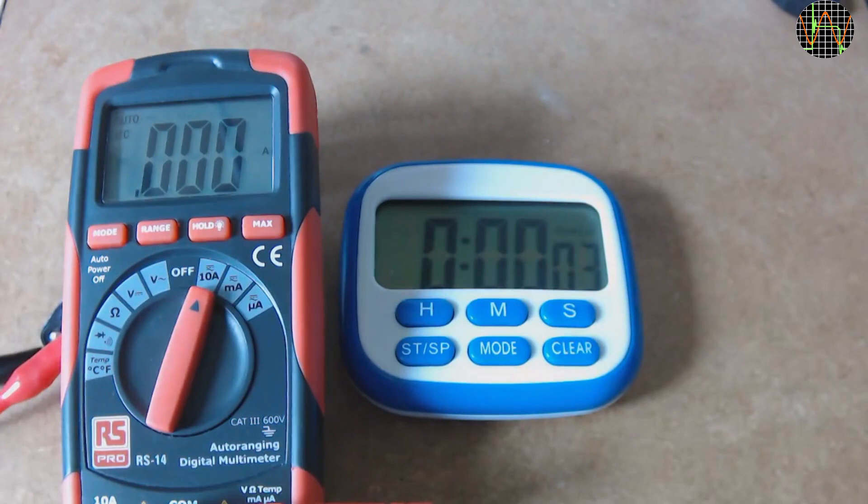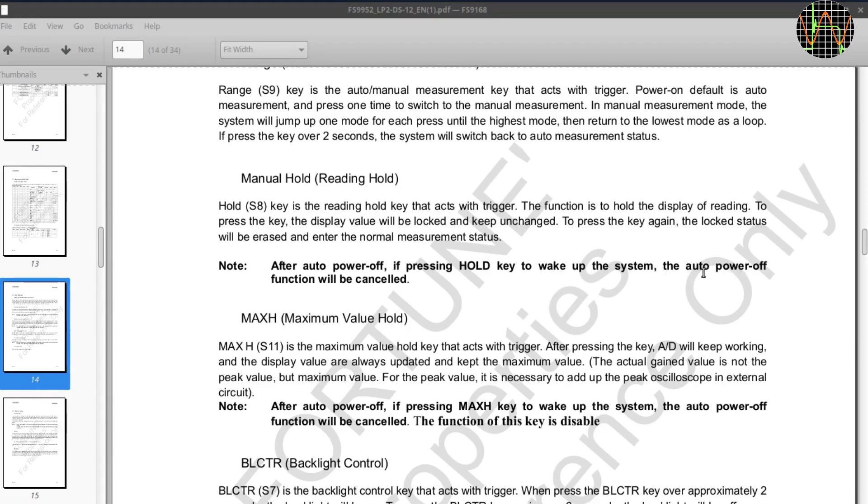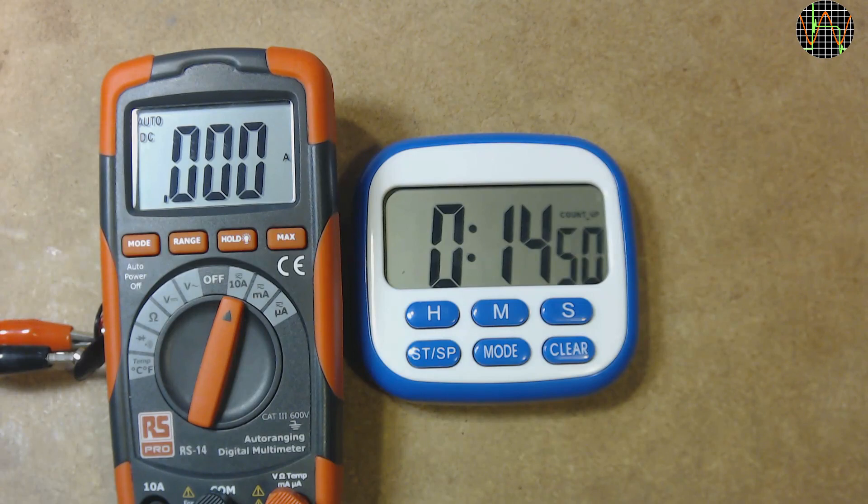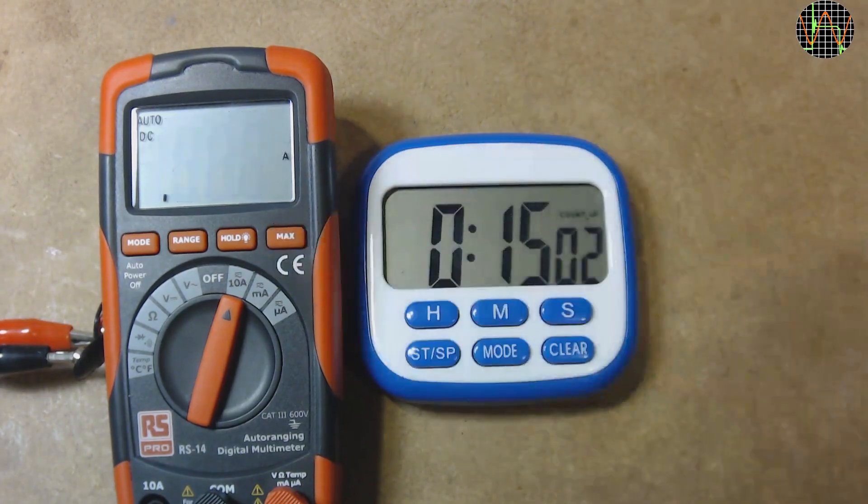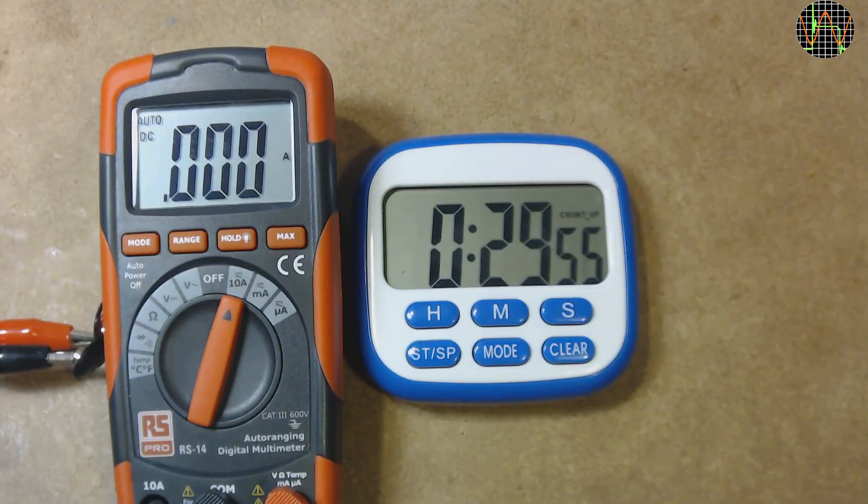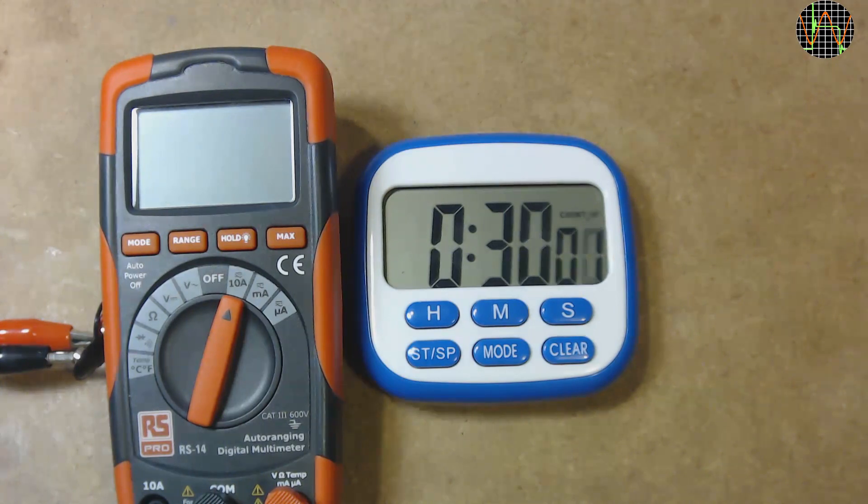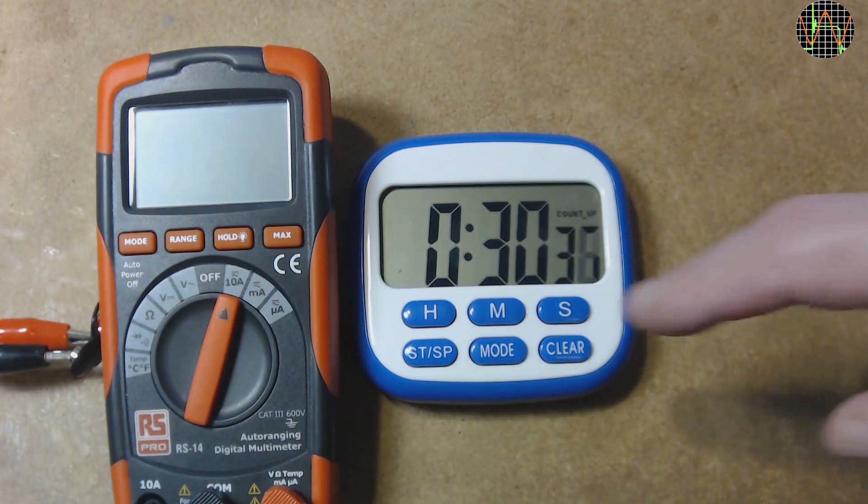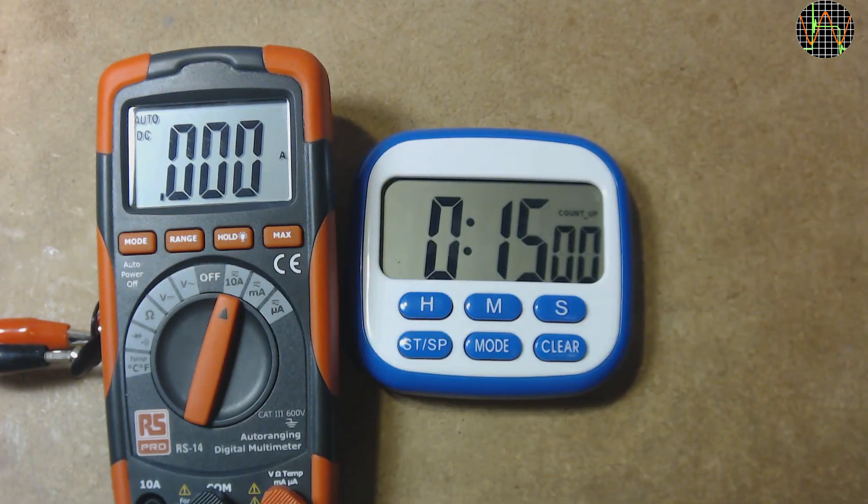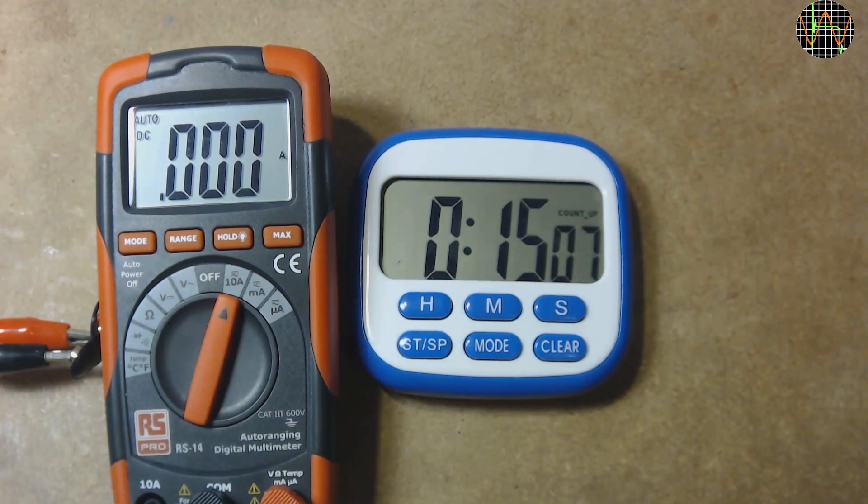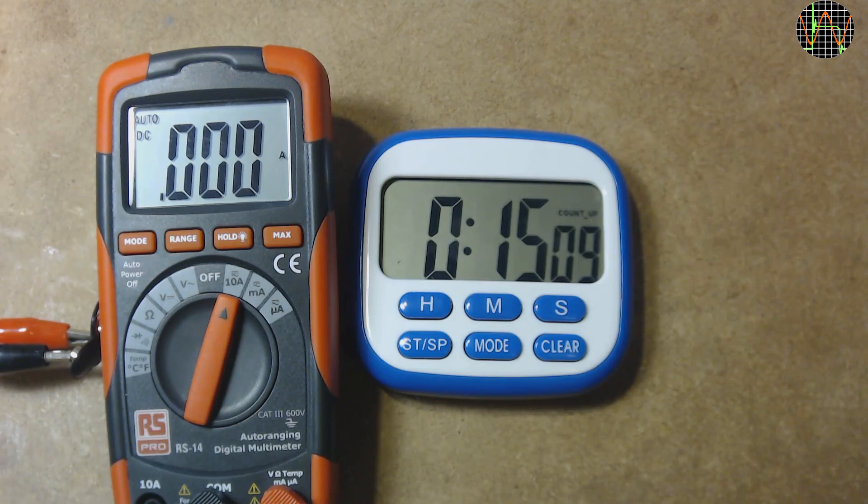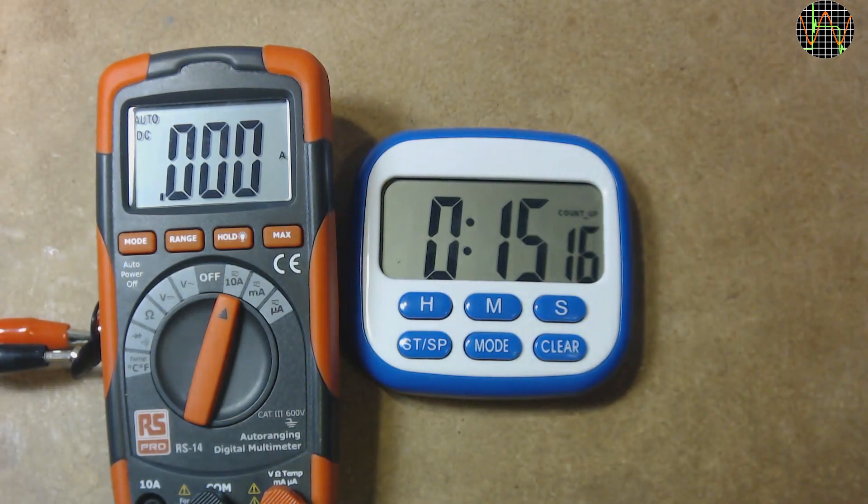But that means, if you move the selector from volts or resistance to current, APO is re-enabled because you go via the off position. And of course, the same happens when you move the selector the other way. The datasheet is a bit confusing regarding the behaviour of the hold and max function with respect to APO. It appears that pressing either one to wake up the meter after an automatic power off will disable APO but while the language for APO and hold is clear enough, I do struggle to make sense of max. By the way, the ease how the meter wakes up after APO by the slightest touch of these buttons means it is not a good idea to rely on APO and throw it in your toolbox without turning it off properly.